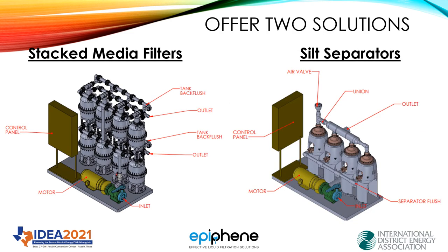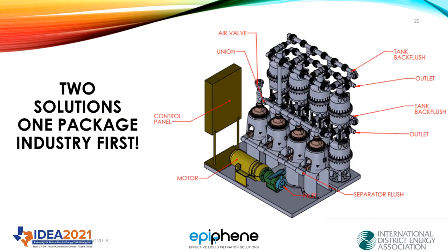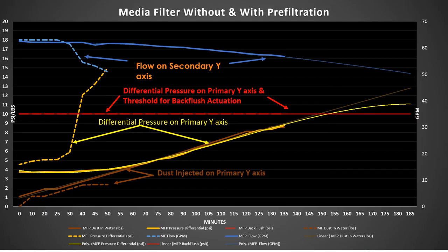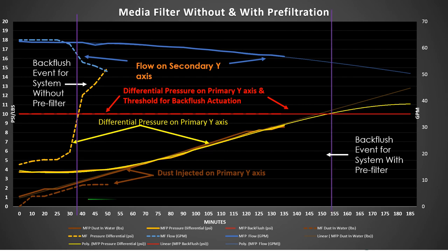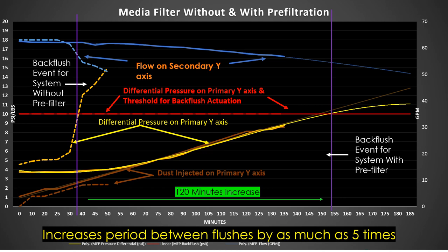We can offer skidded systems for media or for separation. Or in some cases where it's not just separators or not just media filters but a combination of both is needed, we can provide the highest efficiency removal in the industry. If you look at these dashed lines, they represent without a pre-filter from our separator and the solids line with a pre-filter. Without a pre-filter, we would have had to flush in 30 minutes. With a pre-filter, we could have gone all the way out to 150 minutes — that's over two hours difference, and actually five times longer for this filter to run.